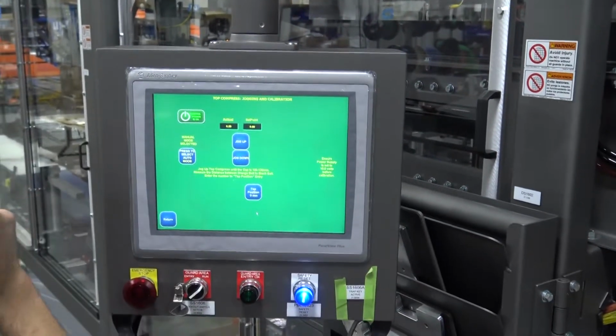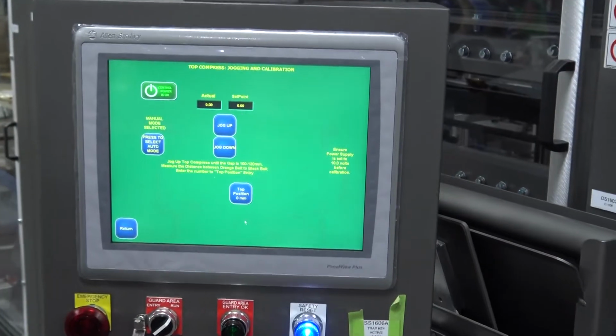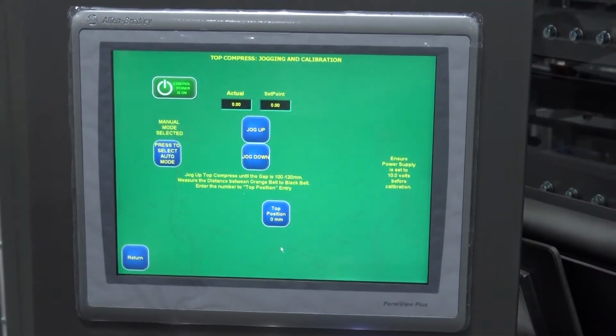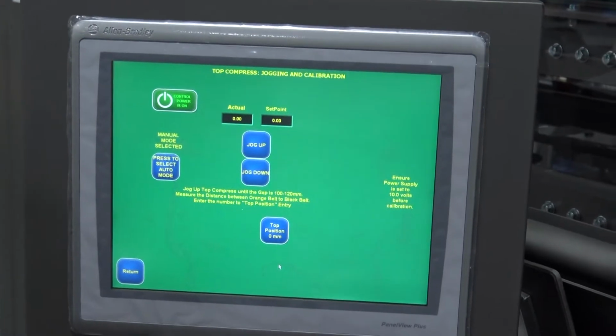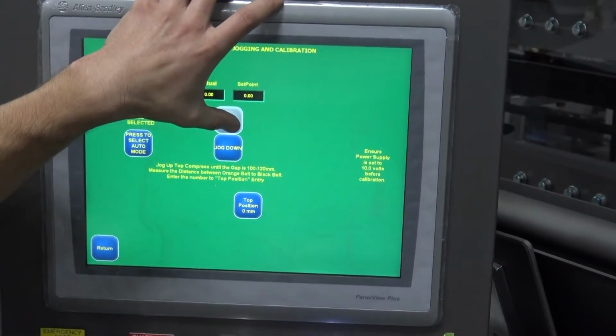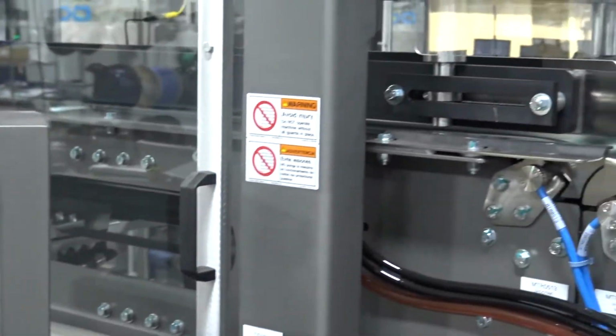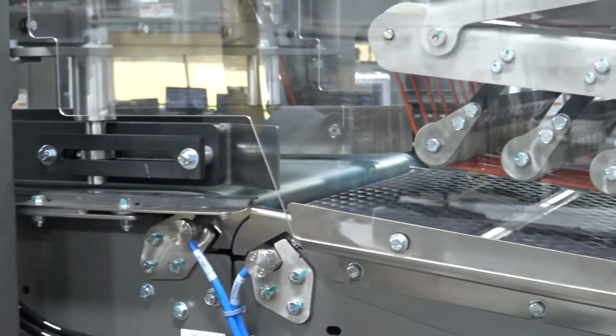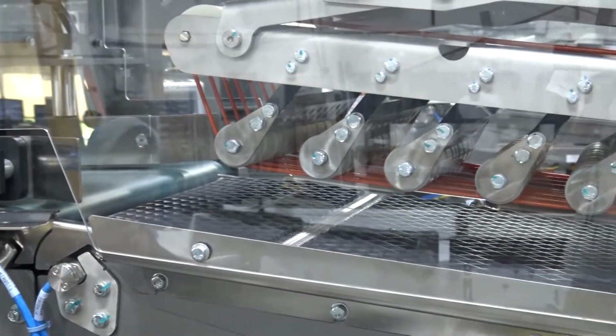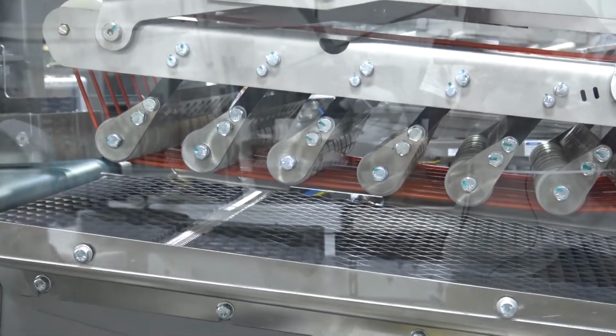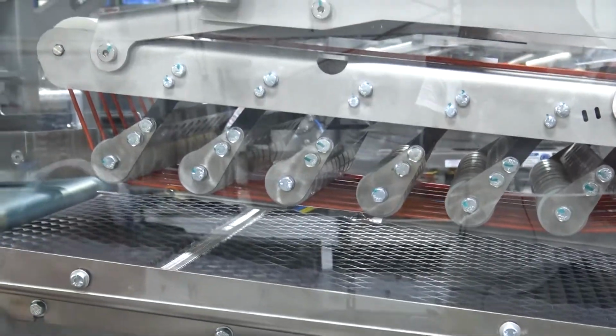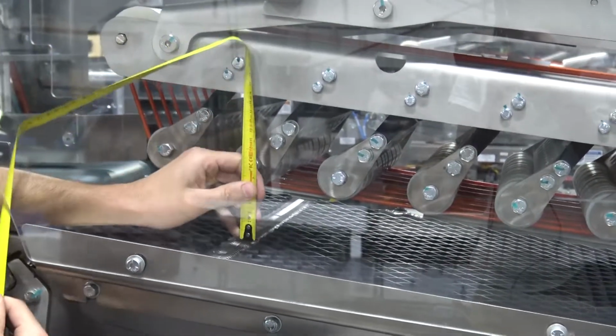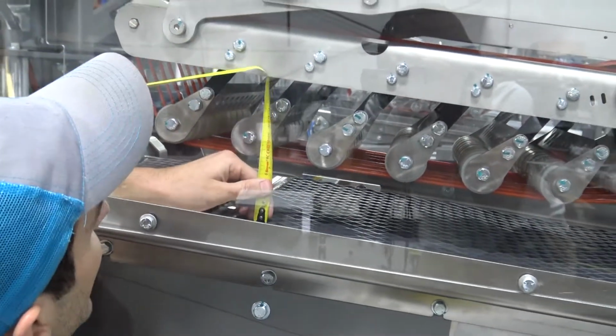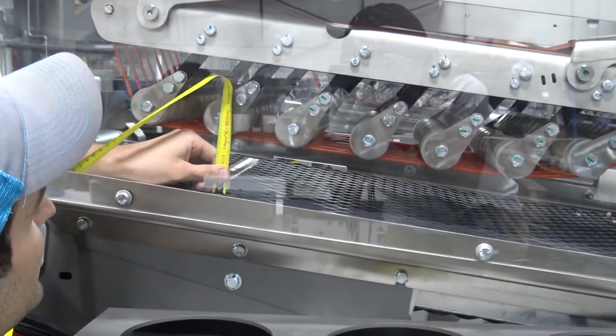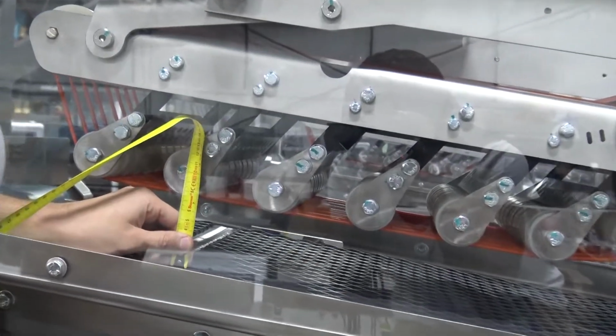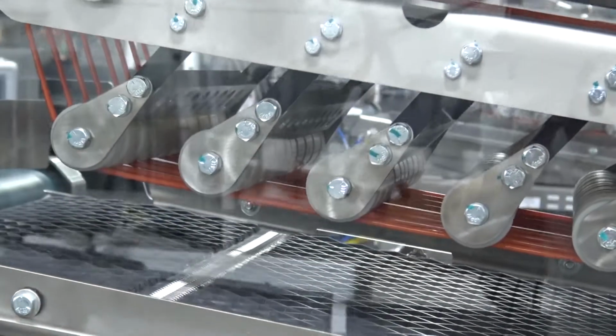And now the instructions tell me to jog the top compress until we're between 100 and 120 millimeters above that vacuum belt, that black belt. And that's about 4 to 5 inches. So you can kind of start by judging it, and be careful. If you jog too far up, then you can fault the actuator. So right there, I'm going to measure that same distance that we just taught the zero position to. I'm going to put my tape measure on the surface of the vacuum belt, and then look for about 100 to 120 millimeters. Right now I'm at about 70, 75 or so. So I'm going to keep on going up.